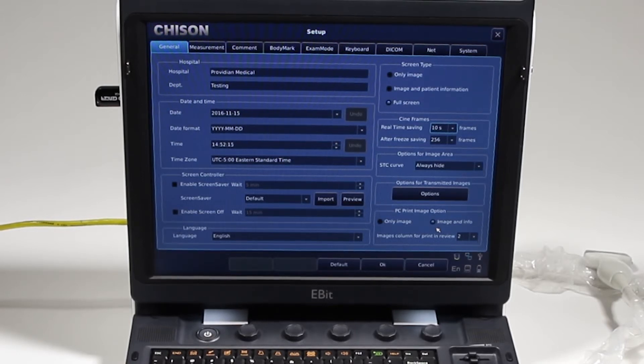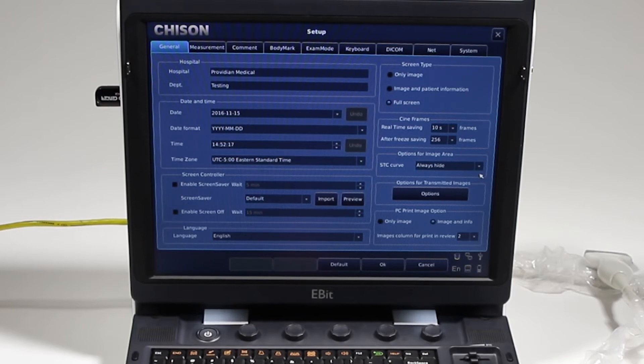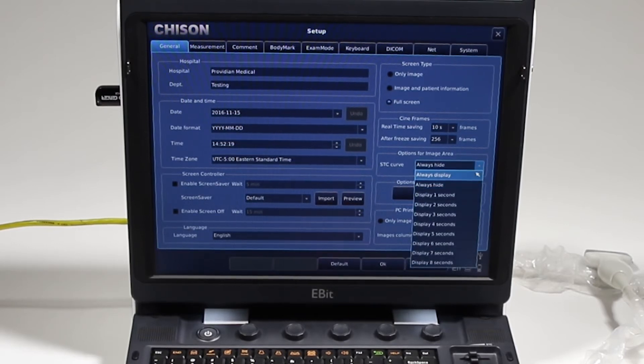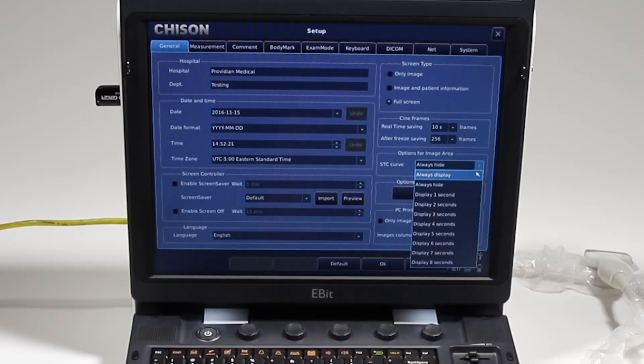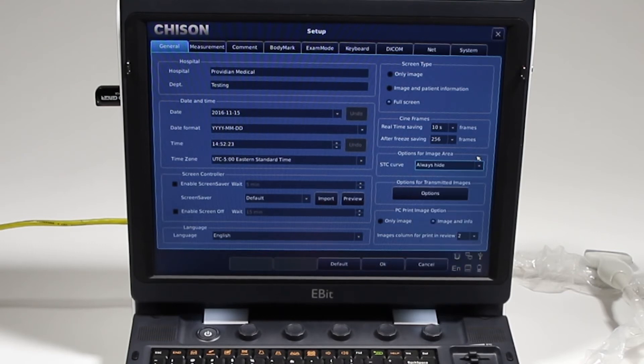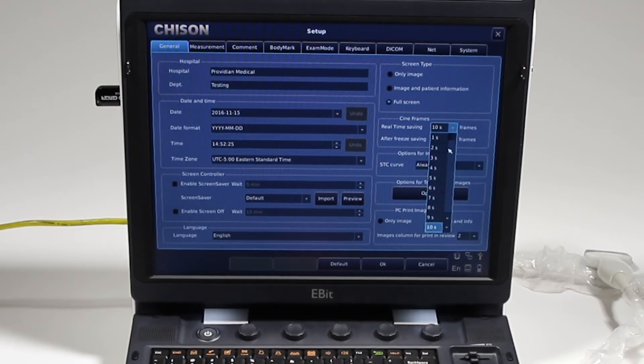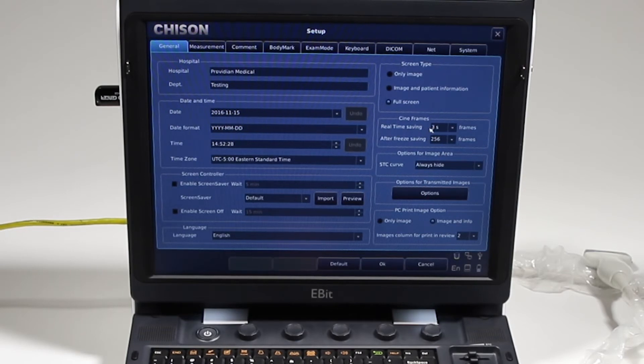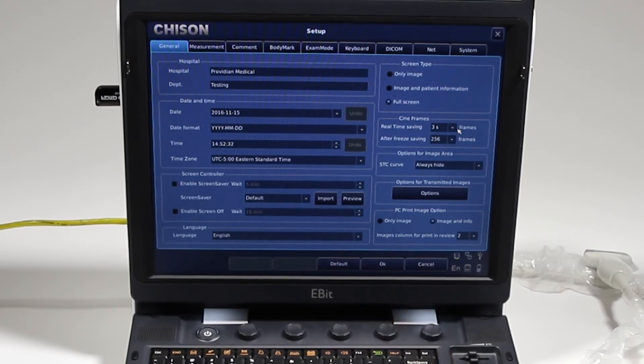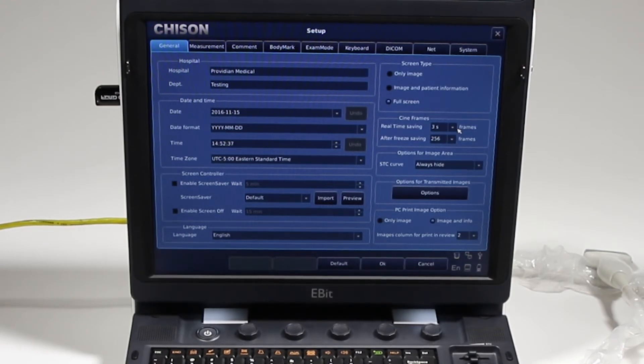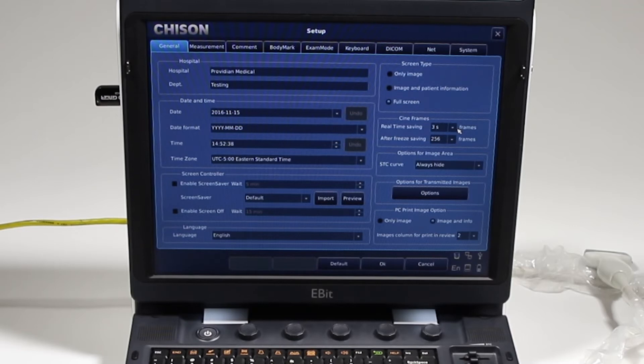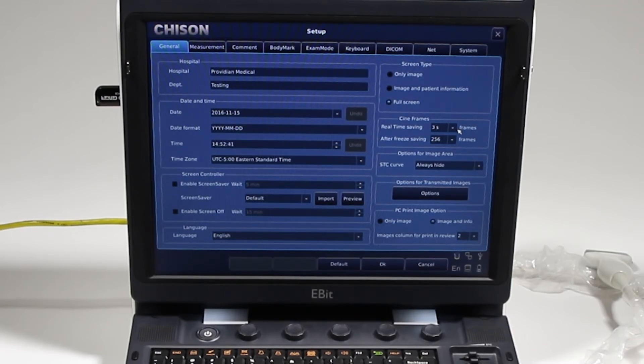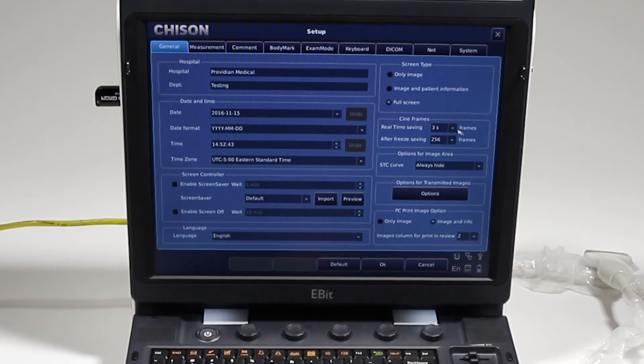Image area: this TGC curve, you can get it to appear on screen and how long you want it to appear on screen. I'm going to check this back to about three seconds. This real-time saving, as we discussed earlier, allows you to hit the cine review key or cine save key while you're doing the exam, so you don't have to freeze and then click and then wait for it to save. You hit save and it's going to save exactly what you're looking at on the screen.